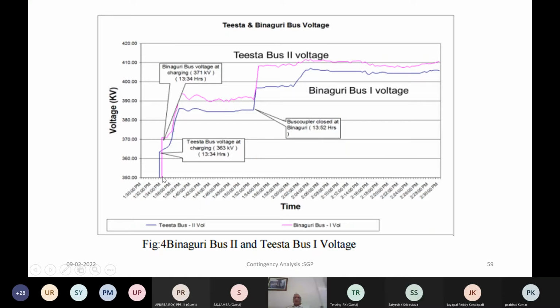You can see how the voltage is built up in this case in a step-by-step manner by manual excitation control. So you can see in steps voltage has been raised. The blue line is actually the voltage at the generating station bus bar, and this purple color is actually the remote end bus bar. So you can see the rise in voltages at the remote end compared to the sending end. So this is the rise in voltage, and step by step it has then been increased slowly to the 400 kV level. You can see at the generating station end, the voltage is built up to the level of say 380, 395 kV or so. But at the remote end, voltage has risen to the 410 level.